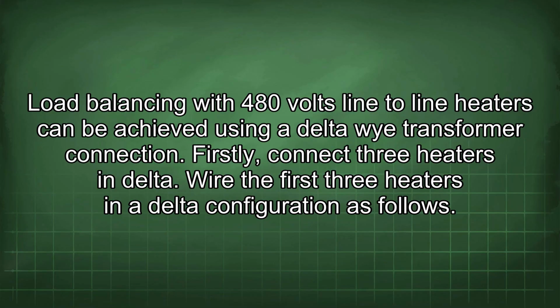Load balancing with 480 volts line-to-line heaters can be achieved using a Delta-Wye transformer connection. Firstly, connect 3 heaters in Delta. Wire the first 3 heaters in a Delta configuration as follows.